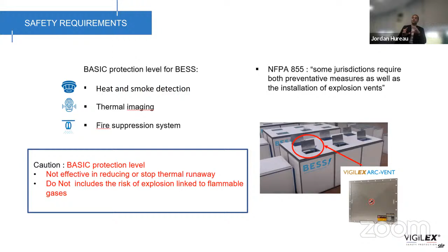Unfortunately, the probability of fires and explosions happening will keep increasing. All the techniques and safety equipment used in the past two cases were not enough to reduce or stop the thermal runaway, and they don't address the risk of explosion linked to flammable gases. The NFPA 855 states that some jurisdictions require both preventative measures and the installation of explosion vents. That's why at Stif we developed, a few years ago, a range of products to mitigate and stop the risk of explosion.